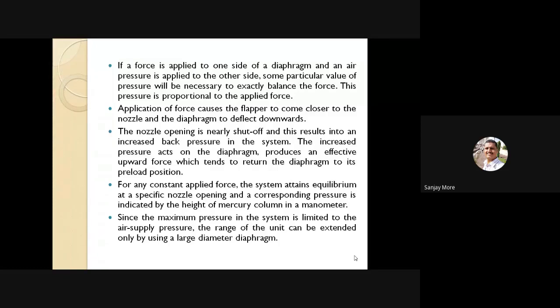Last sentence. Since the maximum pressure in the system is limited to the air supply pressure, the range of the unit can be extended only by using a large diameter diaphragm.